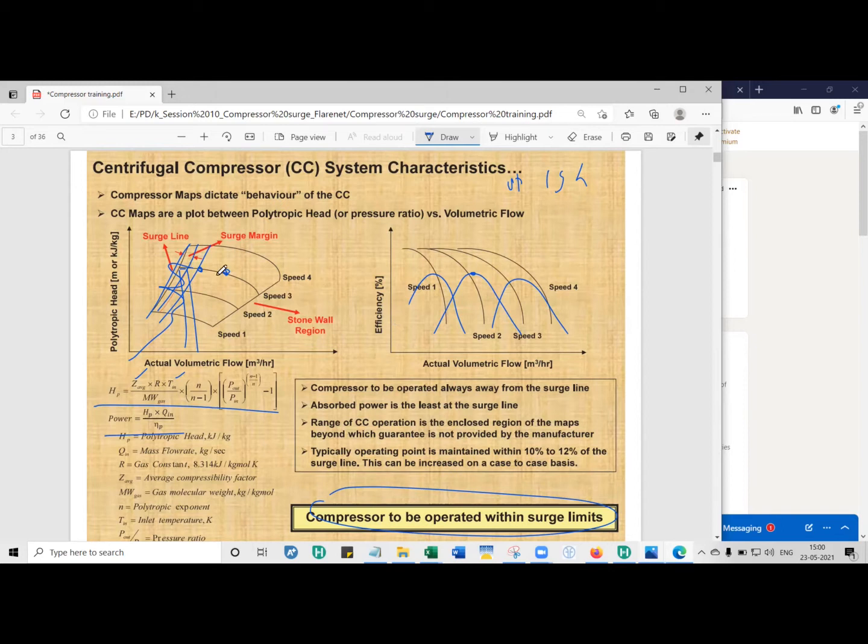When a manufacturer provides you with the performance curves, the polytropic head versus the actual volumetric flow rate, the operating point must operate as close as possible to the maximum efficiency. At lower efficiencies, you require more power to compress the gas. And on a final note, always operate the gas compressor within the allowable limits to prevent mechanical damage.